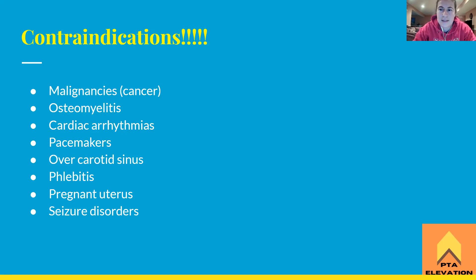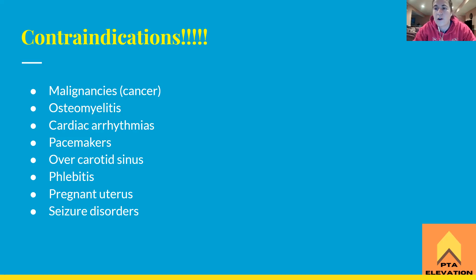Cancer and malignancies — this is because we haven't tested e-STEM on people with cancer to confirm it won't make things worse. The thought process is that e-STEM would increase blood flow to the area and therefore increase the chance of metastasis, so we don't put e-STEM on anybody with a malignancy.